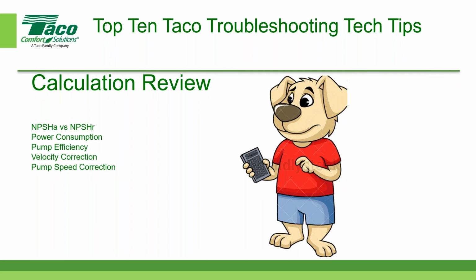We also want to know what the pump efficiency is. And when we do our calculation review, we'd also make a correction for the velocity, because remember that the outlet velocity on an end suction pump will be higher than the inlet. The overwhelming majority of end suction pumps. I don't know if that's true 100% of the time, Brett. Maybe someone out there in the audience could tell me, but at least I think in our base mounted end suction pumps, our inlet is always larger than our outlet, so you'd have to make a velocity correction.